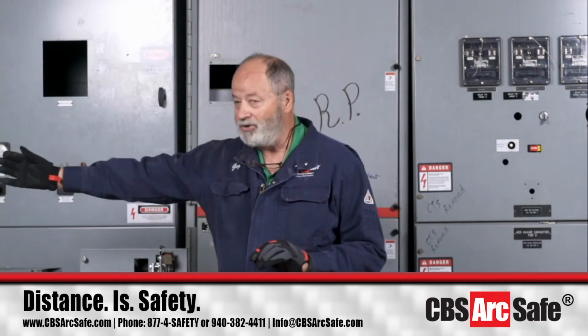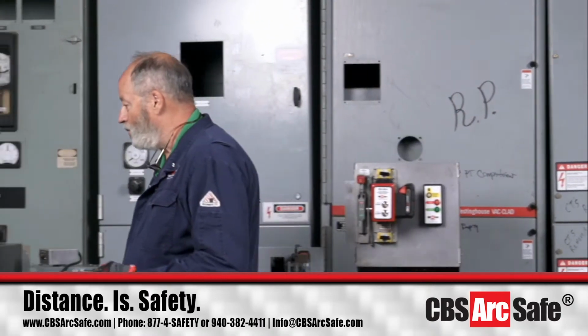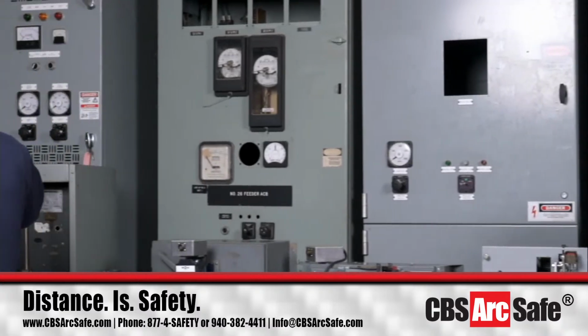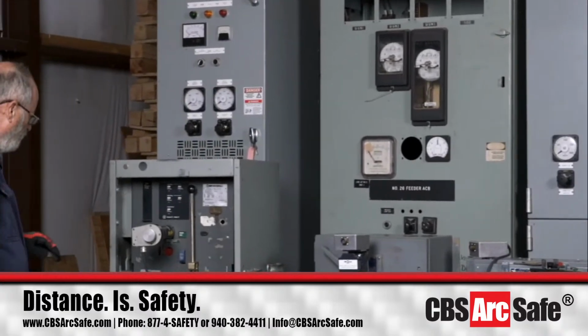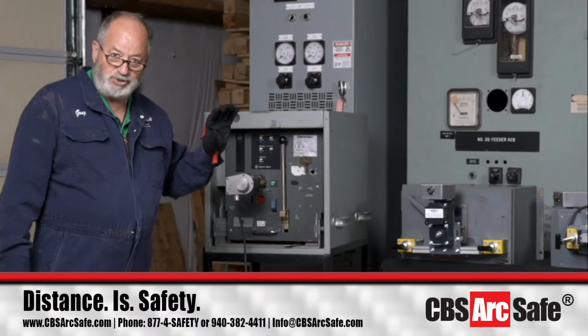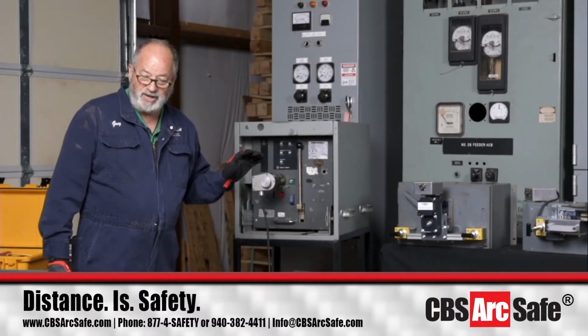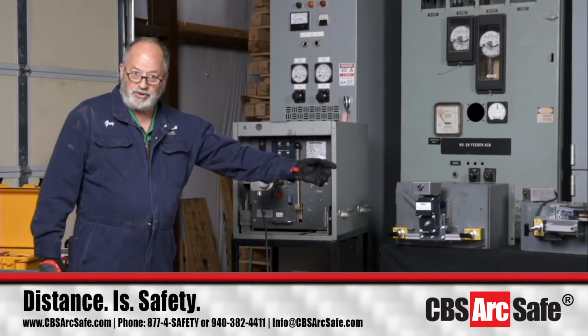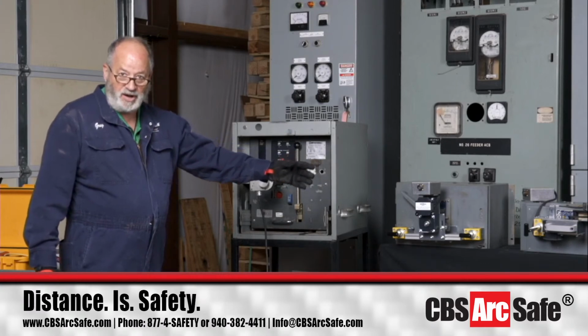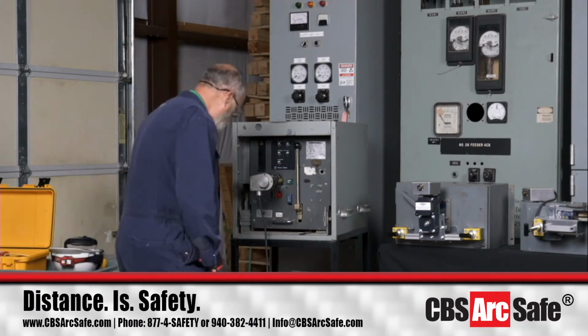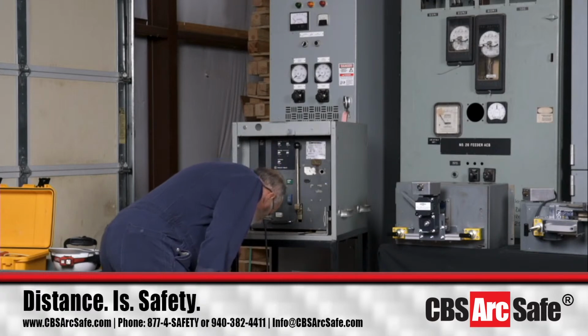So we're going to start out first with our DSR1 for the RS3 system. Normally what I'd tell everybody is make sure you look at what your arc flash hazard boundary is and be outside of that when you're going to do this type of thing for real on live equipment. So we're going to turn the system on.